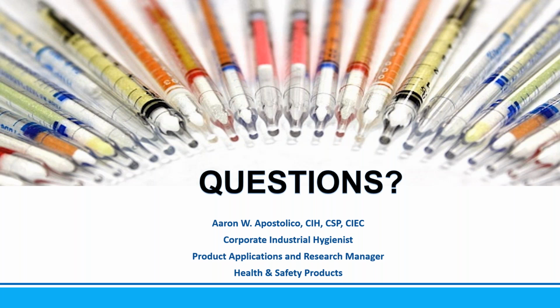This is why we really recommend staying in brand, because that detector tube is specifically calibrated based on the manufacturer's hand pump. So when you start looking at cross-compatible piston pumps, for example, that it might fit or might work functionally, the actual results could be impacted by using a mismatched brand. Okay. That asker particularly questioned about Honeywell. And the next one was asking about Kitagawa and Gas Tech and so forth. I think you answered all of that.